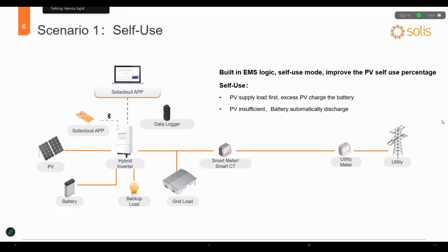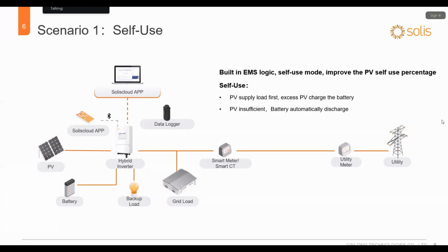So for scenario 1, is the backup load or the grid load the first priority? Okay, when you have the self-use system, the backup load is the first priority. If the PV power and the battery are enough, then you can go for the grid load.